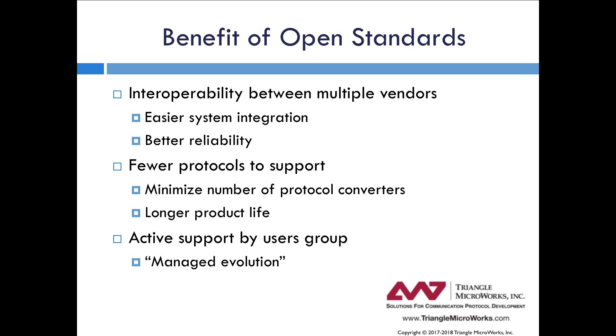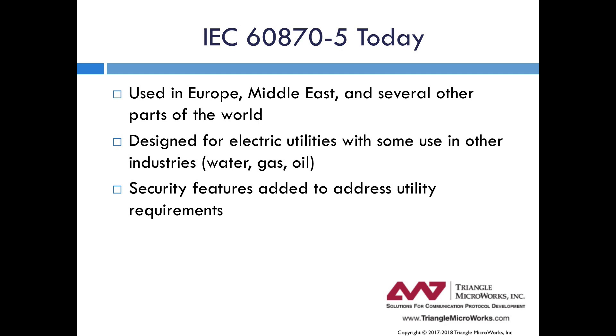In the case of IEC 60870-5, there's really not an official users group. The protocol is controlled by the IEC working group and that working group meets on an as-needed basis. In recent years, the working group has mostly been focused on work relating to security features. 60870-5 is primarily used in Europe and in the Middle East, but in several other parts of the world as well. Basically, it's either DNP3 or 60870-5 which is primarily used for distributed SCADA systems. A general rule of thumb is that English-speaking countries tend to prefer DNP3, whereas non-English-speaking countries tend to prefer 60870-5. 60870-5 is being used primarily for electric utilities, but we are seeing it used in some other industries as well. DNP3 went into other industries a little bit faster, but 60870-5 is spreading, and security features have been recently added to the protocol.